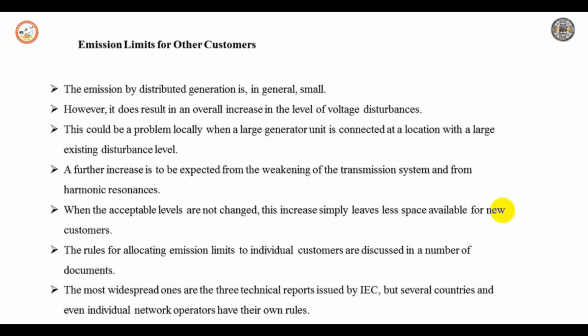When the acceptable levels are not changed, this simply leaves less space available for new customers. The rules for allocating emission limits to individual customers are discussed in a number of documents. The most widespread ones are the three technical reports issued by IEC, but several countries and even individual network operators have their own rules. A common approach is to choose a level that is seen as the highest acceptable level after the connection of new customers.